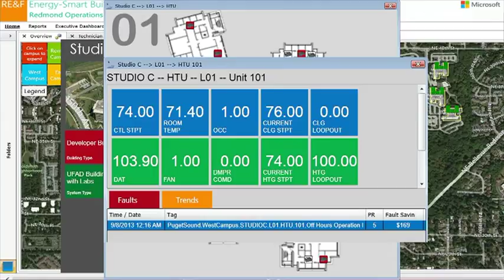I have 20,000 of these boxes across the campus, and once enough of them start running out of spec or out of design, you're bringing on all your air handler equipment as well. So not only do I have a $169 fault, I have a $50,000 fault. So I can look at it at a building level, which is great.